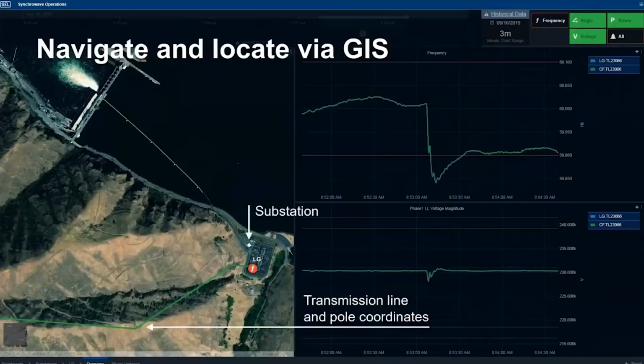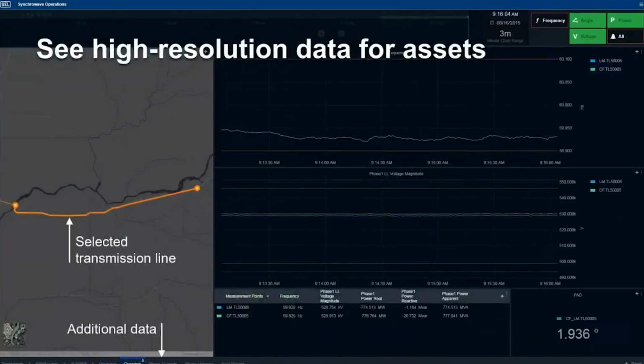Next, again, the software incorporates the latest in GIS technology. So you can look at your information from a GIS point of view. Again, you can see that this is my substation. I also have pole coordinates for all my transmission lines. So I can find or locate the problem areas really quick with this software. And again, if I get a one-click notification and I'm not sure what the notification is for, or I'm not immediately able to identify what the problem area is or what's causing the alarm, I can actually click on my transmission line or any asset for that matter, and it gives me a bunch of information about that asset.